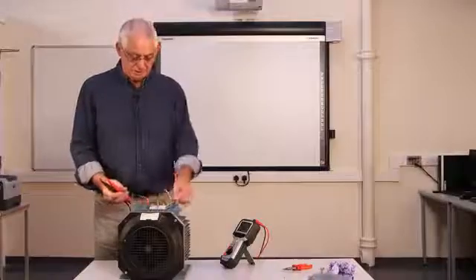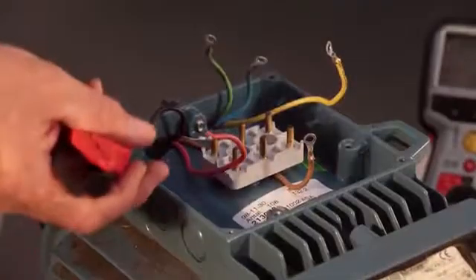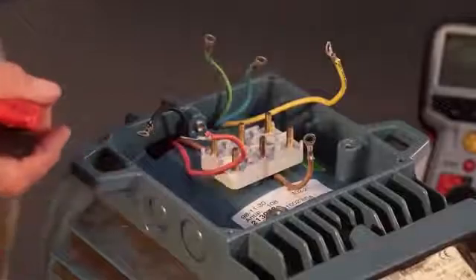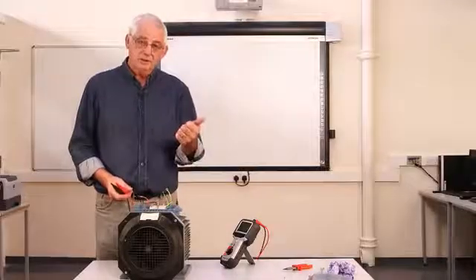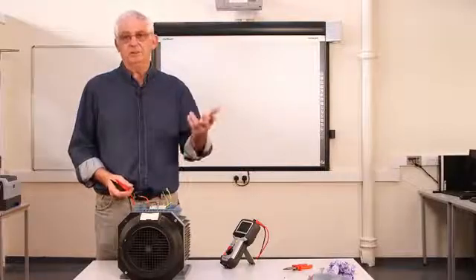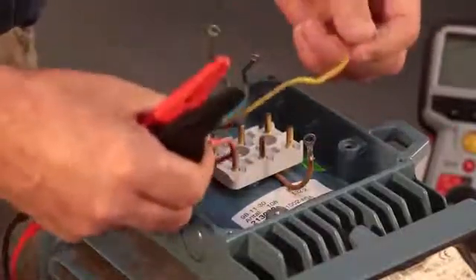Here we've got a motor and you can see that there's six ends of wire, and each of those ends belongs to a winding. So as we've seen we've got V1, W1, U1, U2, V2, W2, but we've no idea which of these two form one complete winding, so of course we need to find out.